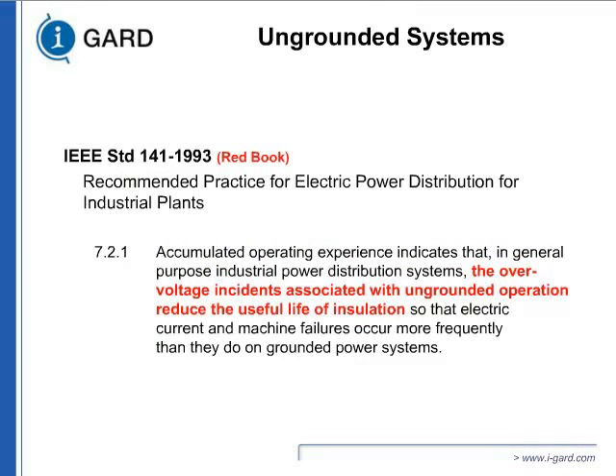Normally, overvoltage always degrades the insulation, reduces the life, and most of the time will cause a failure. Insulation system is designed only for certain voltages. After that, for example, a 480 volt system will probably fail very soon if you consistently keep giving it high voltage pulses. And these failures happen more frequently than in the grounded power system, because grounded power systems, whether they're solid grounded or resistance grounded, will tend to clamp the voltage. Ungrounded system does not do that. Okay?